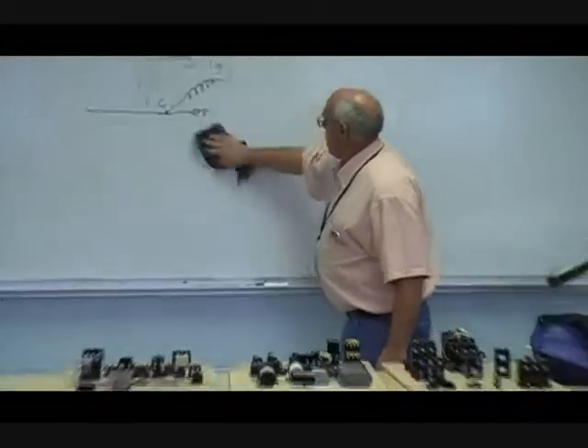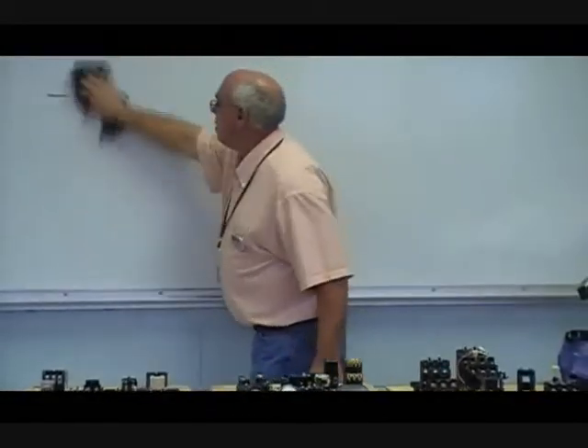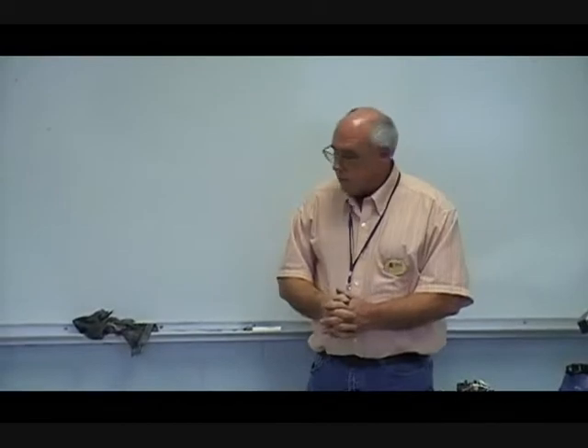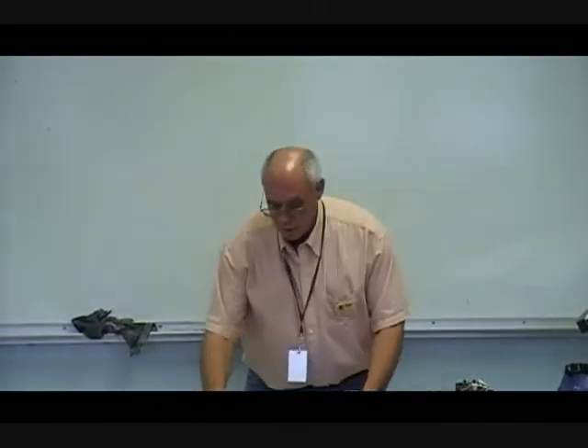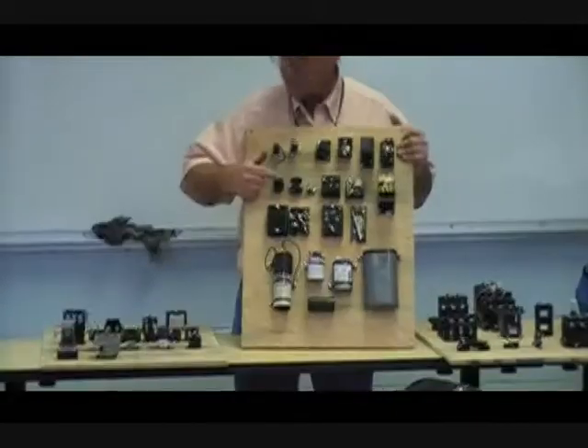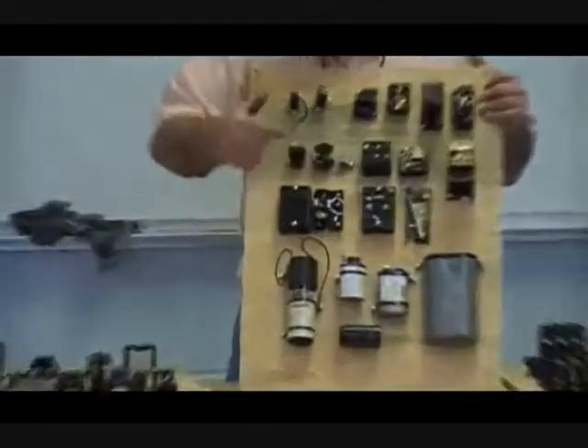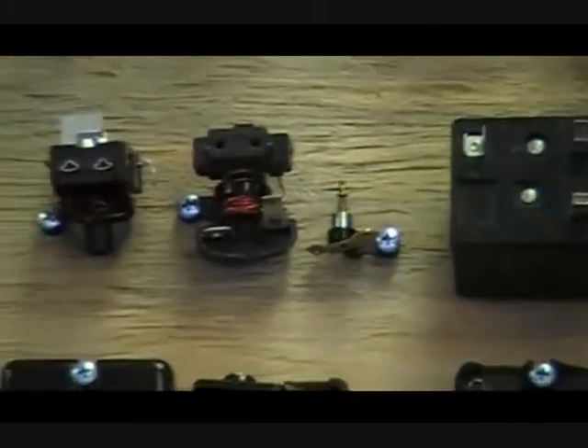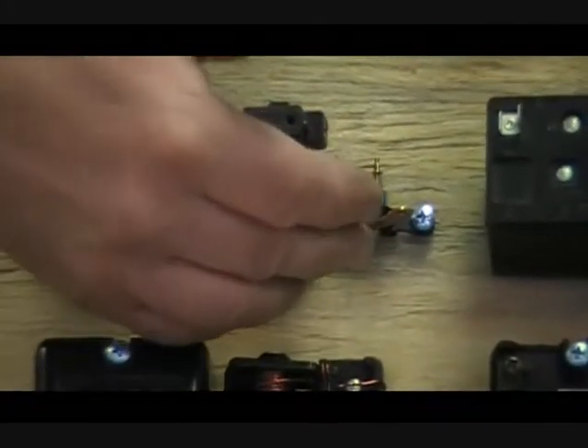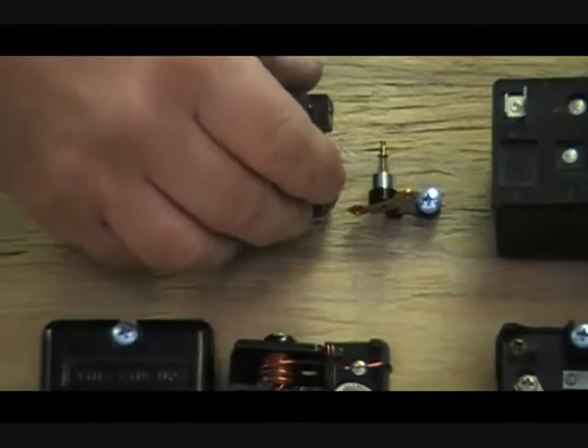Now, the hot wire relay is almost a mystery to us. Now, it is a very complicated device to troubleshoot. Whereas, the other two relays are very easy to troubleshoot. I didn't say this, but we can measure the coil, the resistance of the coil to see if it's good. We can measure the contacts on a current relay to see if they're open when they're de-energized. In fact, if you have this loose, you can...